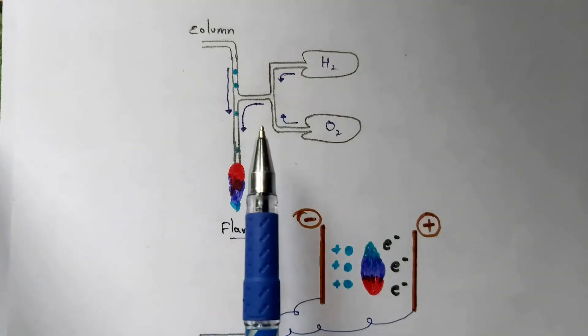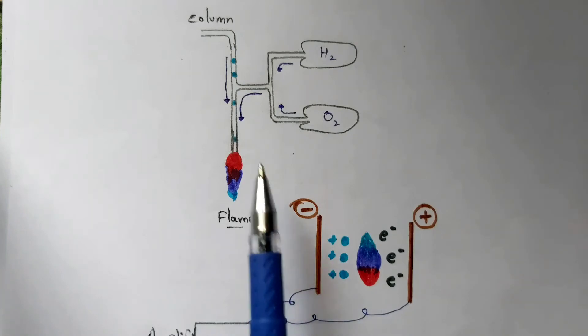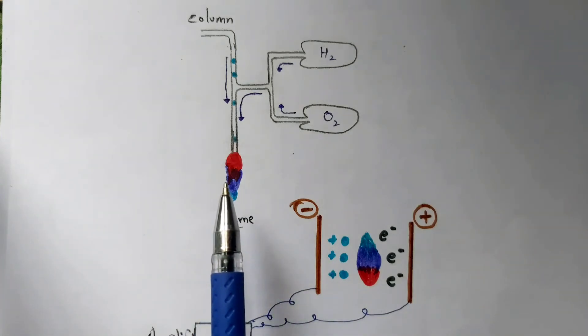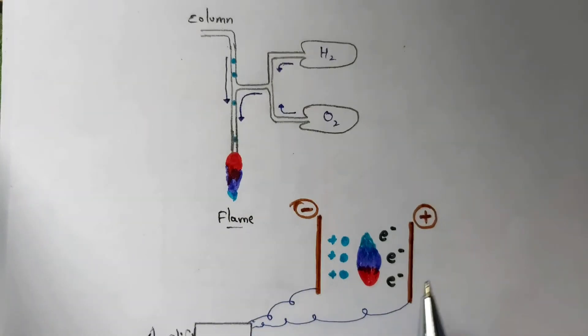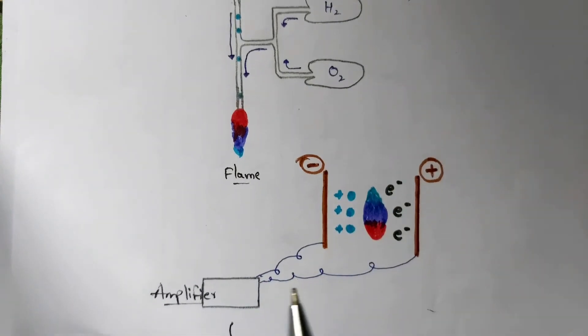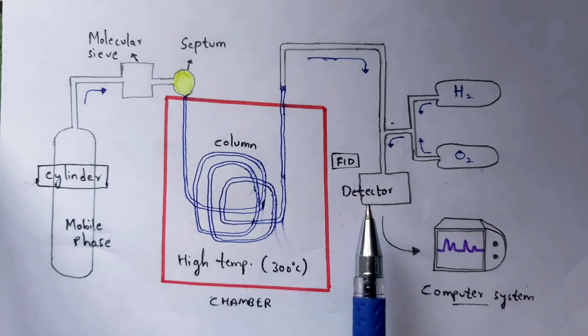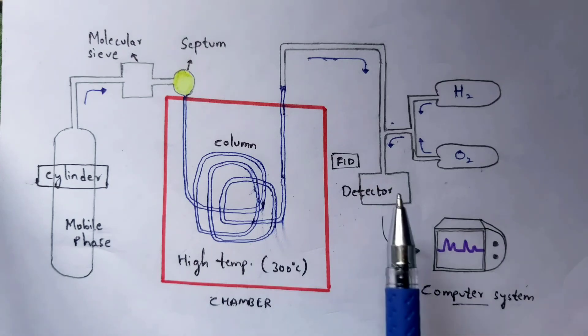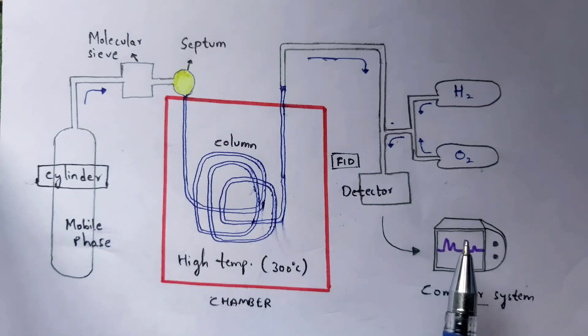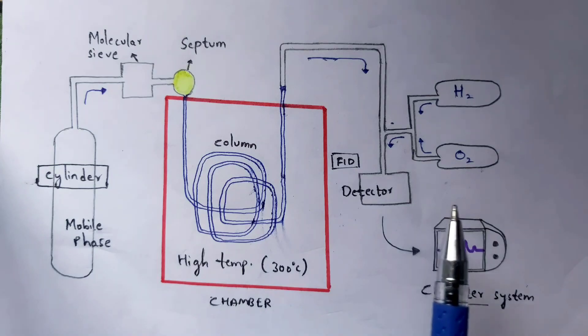Due to the combination of these three inlets, when the molecules pass through, a flame is produced. The molecules interact with this flame, leading to ionization — meaning electrons get separated. Positive and negative electrodes are installed and connected to an amplifier. The amplifier is connected to a computer system where graphical representations are automatically generated from the ionization current produced by the flame.